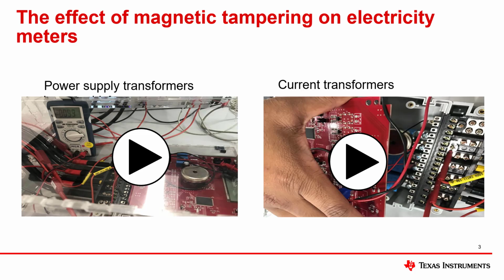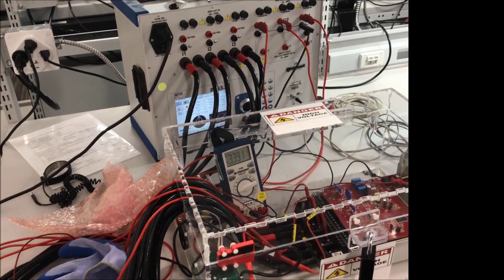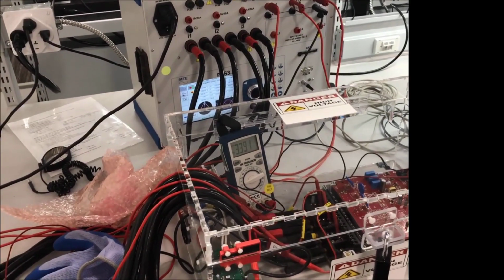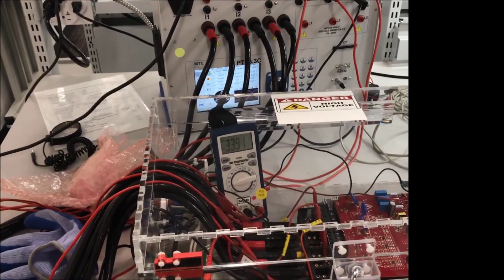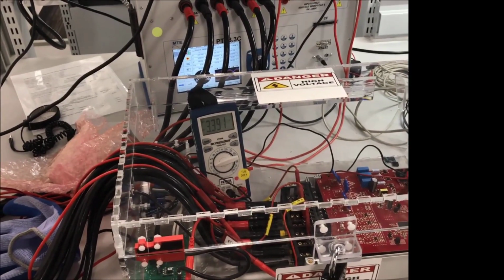One of the most common ways someone tries to tamper with a meter is to apply a magnet on it. This magnet affects transformers in power supplies as well as current transformer current sensors. To demonstrate how a magnet could affect the ferrite core transformer in a power supply, we measured the output voltage of the power supply.